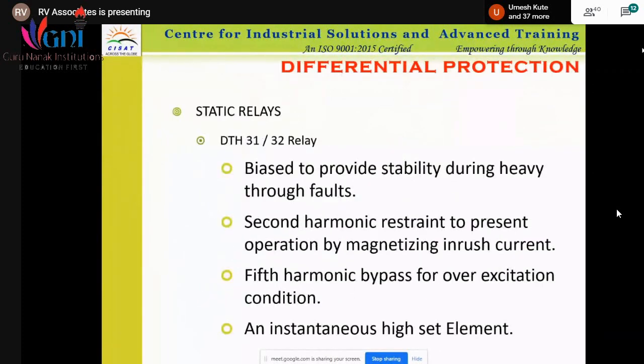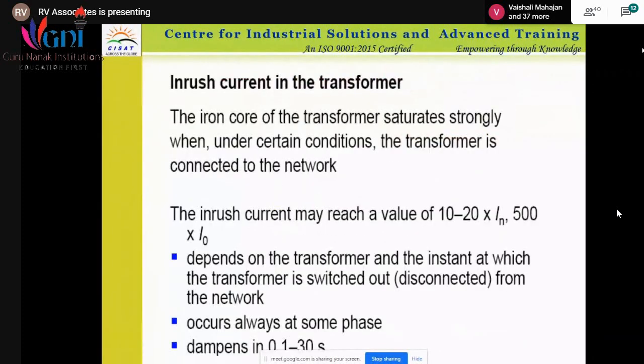Then there is another form of fault, which is because of the inrush current. Normally we know that whenever we do switching, there will be a heavy rise in current. Same thing happens with the transformer, and it is the inrush current. We say it's 10 to 20 times the nominal current, or it can be around 500 times the magnetizing current. Such a current is to be protected against, and that's why inrush current protection is also required.